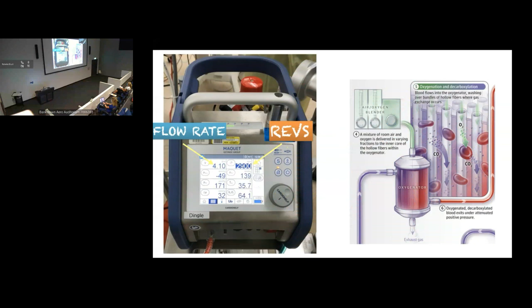And what about CO2 removal? So as I just mentioned, you can see that blood is continuously exposed to a fresh gas flow. So on the left-hand side of the screen, you can see the green tubing that's connected to a flow meter and a gas source, which is connected to the wall. And that green tubing goes all the way to the membrane. And that's all that it is. That's all that is supplying the membrane with oxygen. You control the amount of inspired oxygen by the flow meter and by the blender, the Sechrist blender. It's really as simple as that.